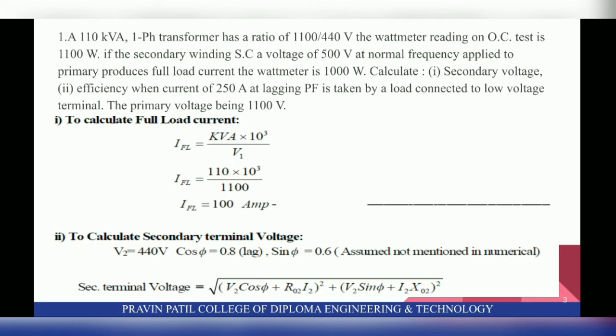The primary voltage being 1100 V. So first, to calculate full load current: IFL is equal to kVA × 10³ / V1. This is the formula to calculate full load current. So IFL = 110 × 10³ / 1100, so IFL becomes 100 Ampere.